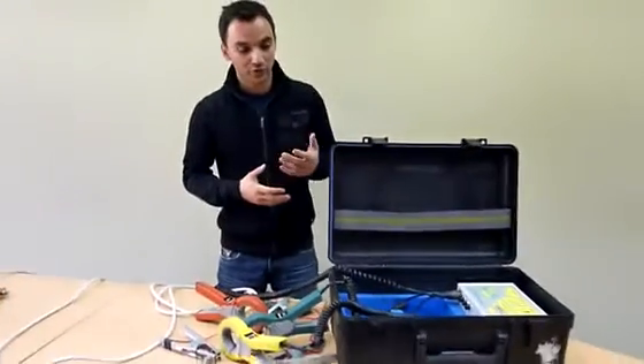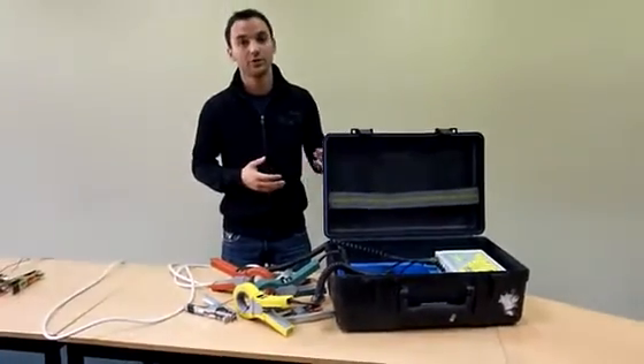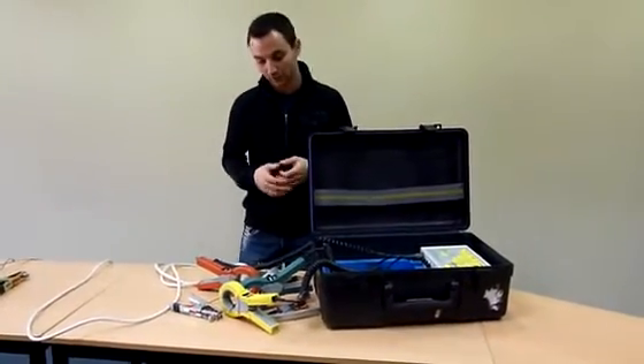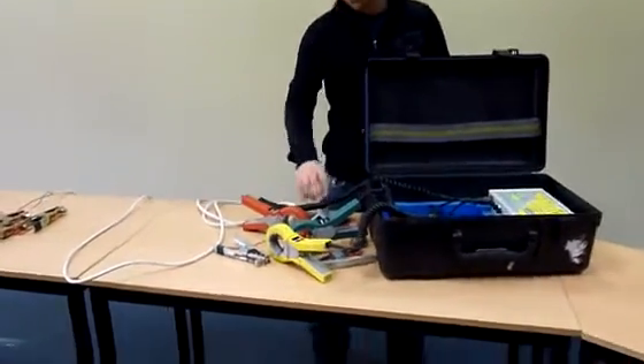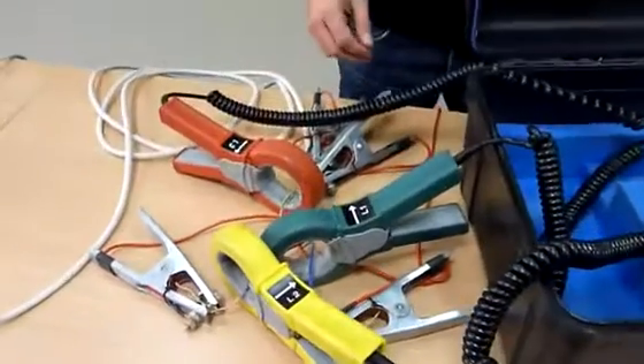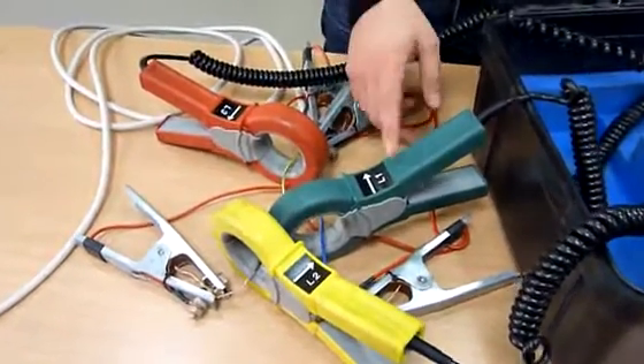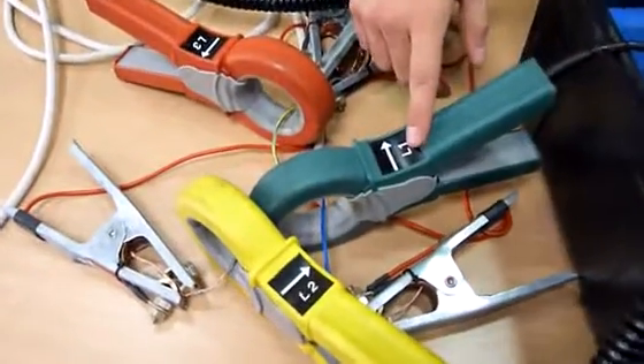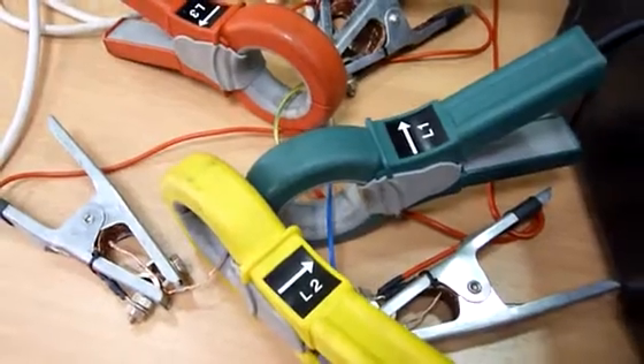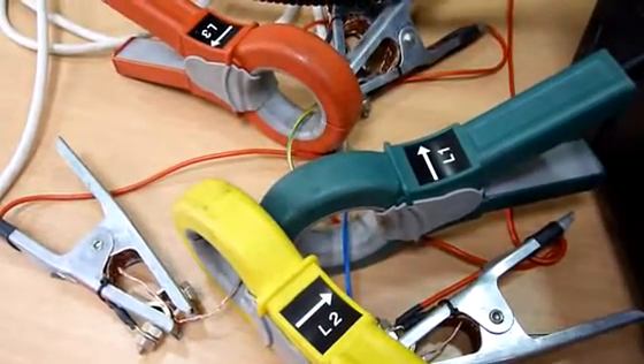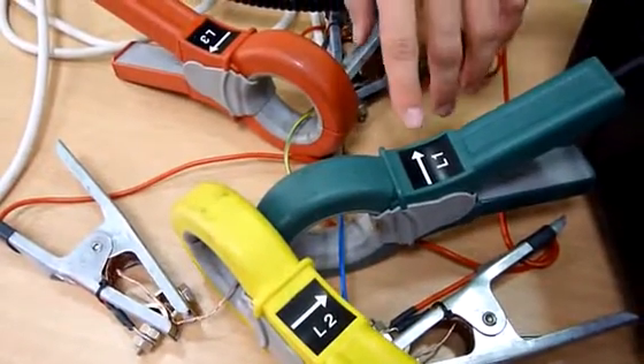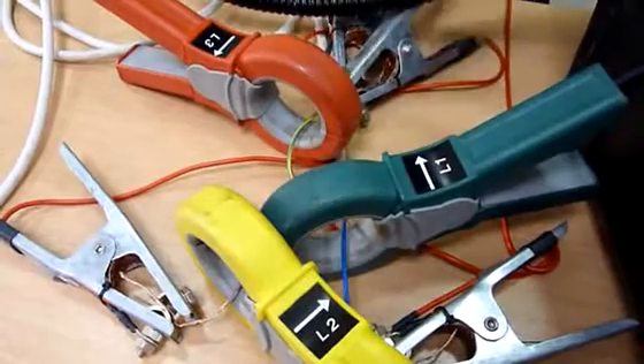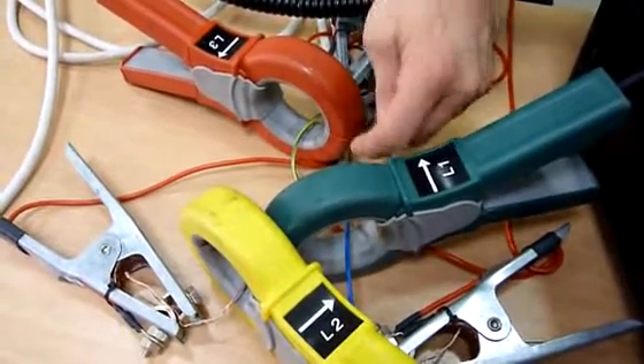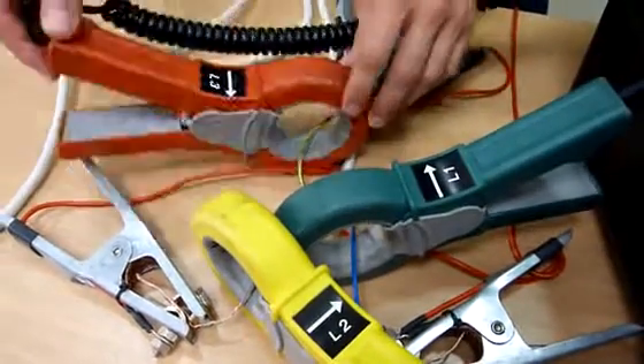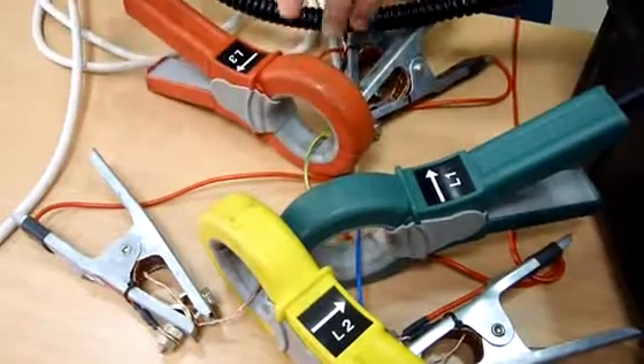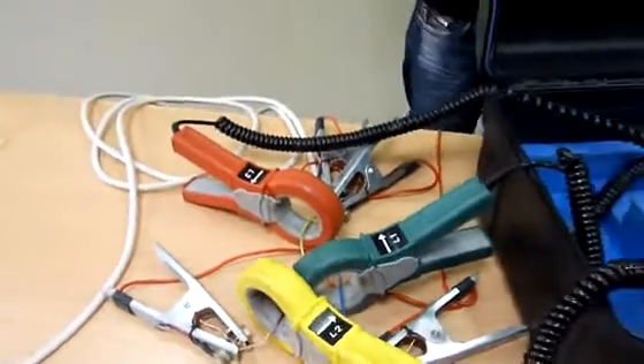First of all, we are going to set up the transmitter. To do this, we connect the clamps on each phase. It's very simple because you have the phase number on each clamp. The only important thing when installing the transmitter is that all the arrows must point the same direction, so here they all go inside the cable the same way.